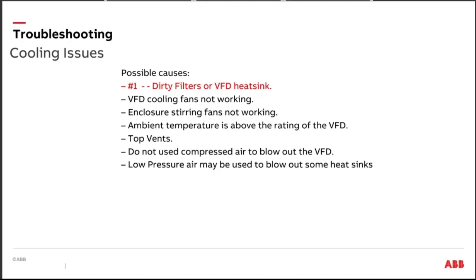Mark and I got to the job site, pulled the cover up on it, and the drives were cankered full of chicken stuff. And it was feathers and chicken poop and just everything that you could not want to imagine. And the drives were cankered full of it. Now, that serves two different problems. Well, first problem, the most obvious, is if the heat sinks can't breathe, I can't get the heat out of the drive, and the drives are going to go down on a thermal condition.